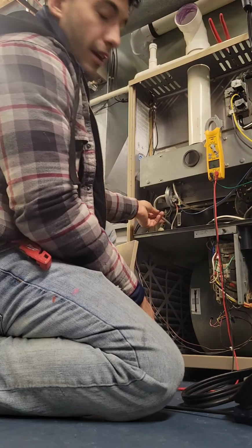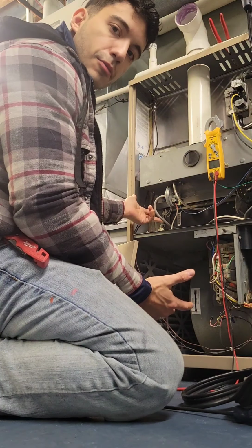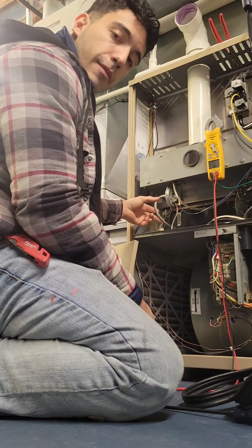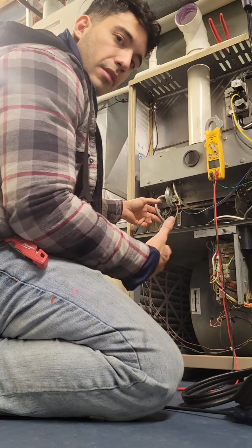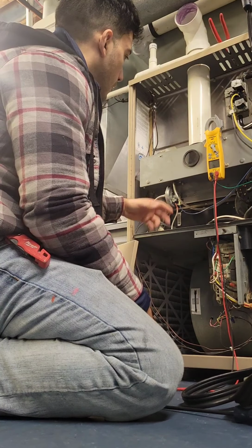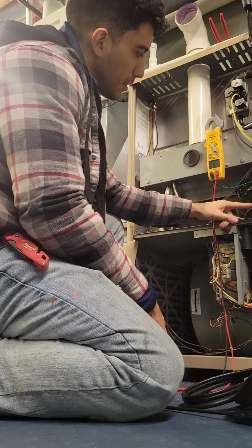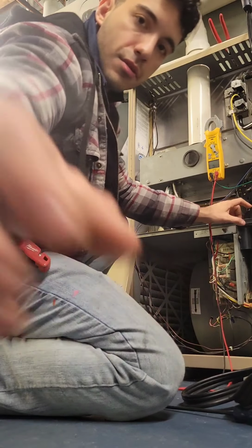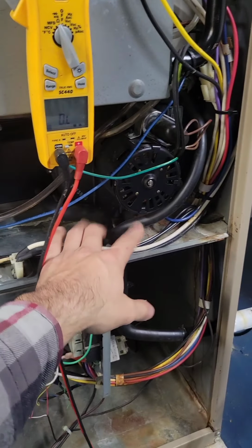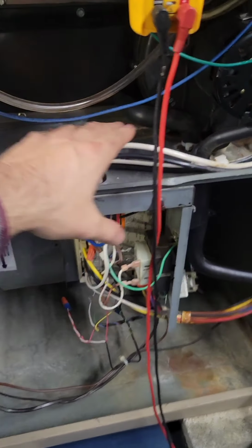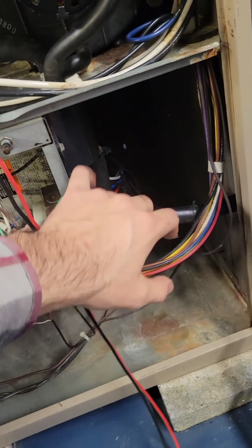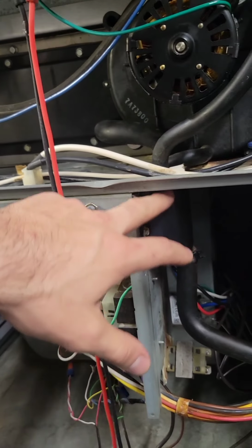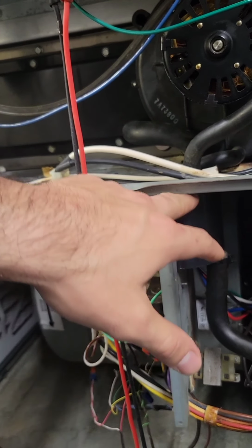Then we obviously check the air hoses, cleaning the air hoses. They're connected to pressure switches, whether positive or negative pressure switches. I tend to take all those off and clean them out. Also in here, you can see there's condensate hoses right here. This condensate hose, that condensate hose, and this condensate hose, they all get cleaned out. This little guy you see right here is actually the condensate trap.